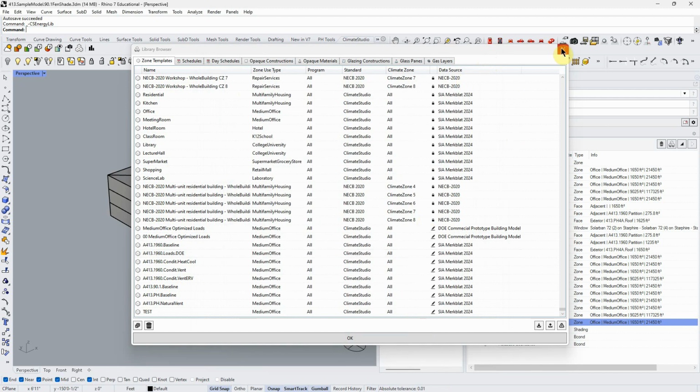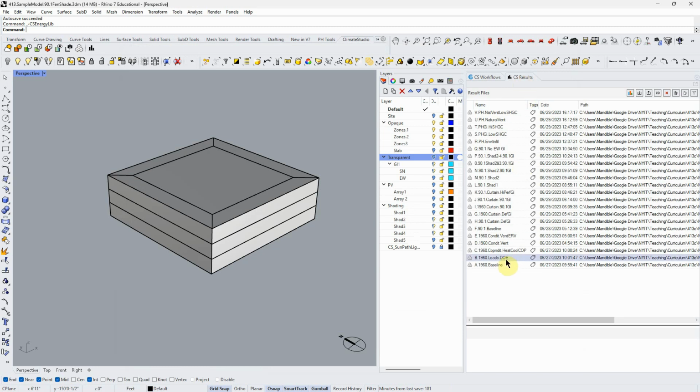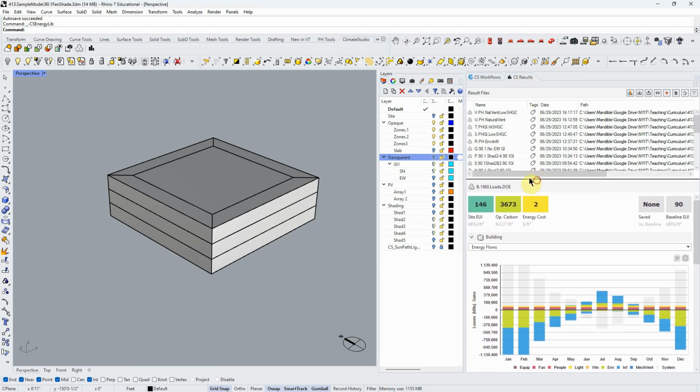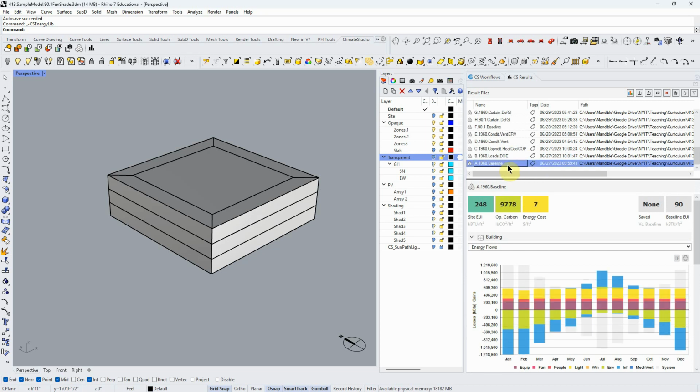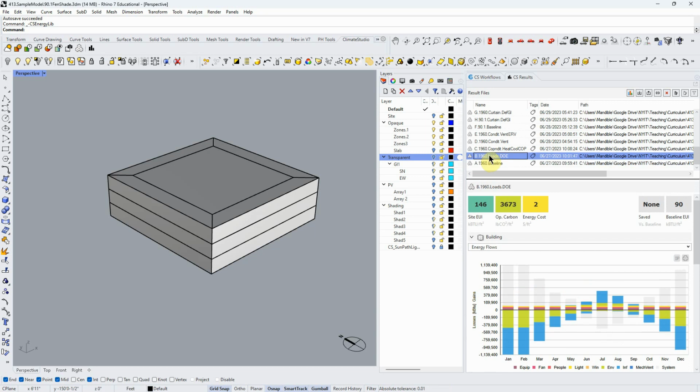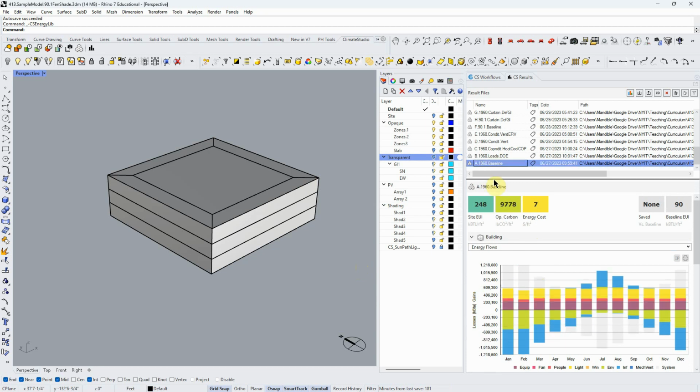So the result of that, and it's the same envelope, is a pretty drastic change from 248 to 146. The point is right now that we're not changing this form at all. All we're doing is internal adjustments, and we can see that. And remember that these values change. So we're at like 609 for the lighting here in January.